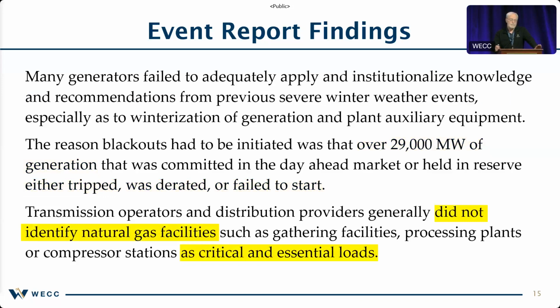And also, what we heard earlier, one of the primary critical loads that they're looking at is natural gas facilities. In this particular case, when they were doing their rotating load sheds, they were impacting the electrical supply to the natural gas facilities. And that electrical supply, because it wasn't identified as a critical load, ended up impacting the natural gas supplies to the gas generators.